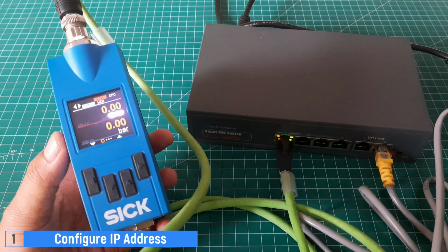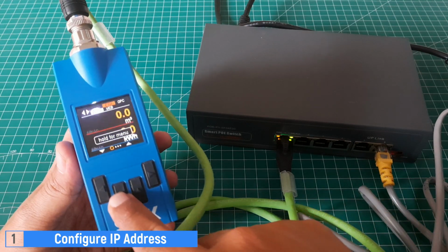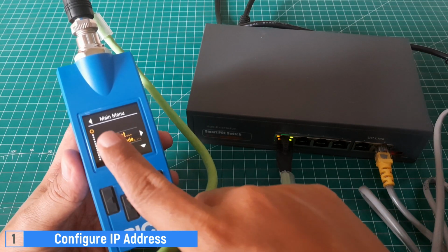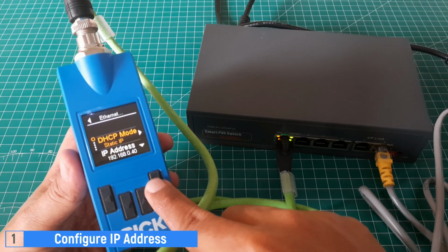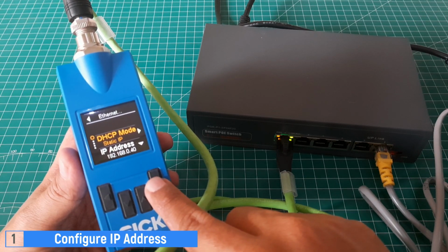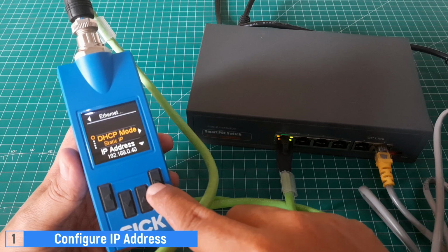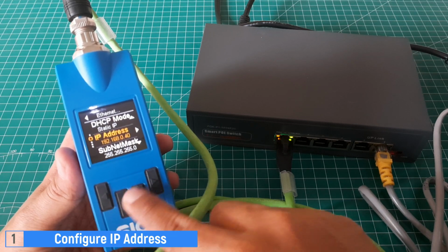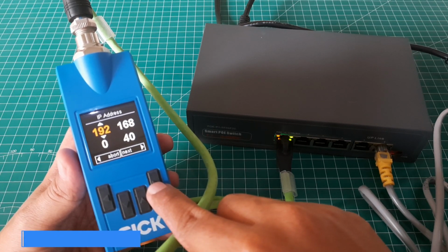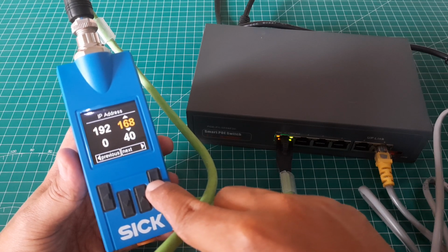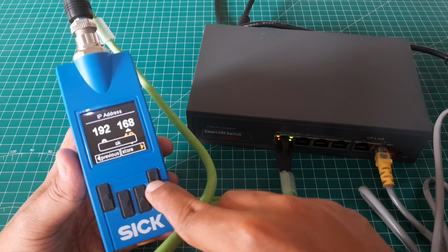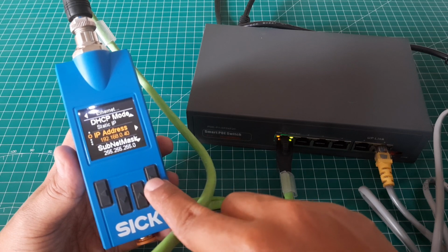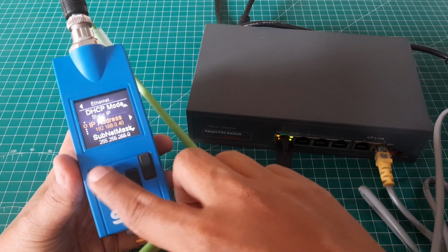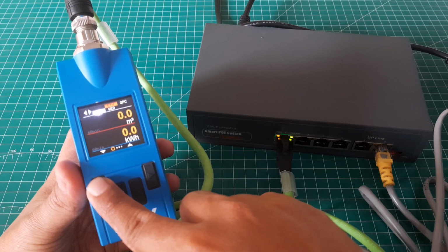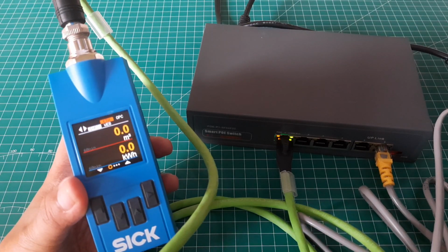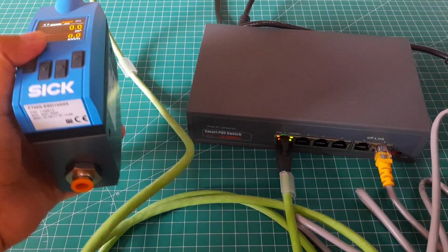The next step is to set the IP address for this device. Hold the button for a few seconds to bring up the settings menu. Then, select Ethernet, and choose DHCP mode to switch to static IP. In the IP address menu, press the right button to start setting the IP address according to the network IP. After setting up the IP address, click the left button to return to the main display. The device is now connected to the network with the configured IP address.